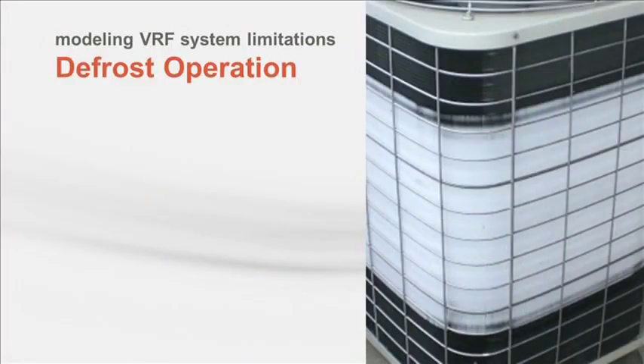Defrost operation allows the outdoor unit to remove any frost and ice buildup on the outdoor coil when operating in the heating mode. Remember that the heat exchanger in the outdoor unit serves as an evaporator when the system is predominantly heating, and this usually occurs when it's cold outside. If a single outdoor unit is used, the system will operate in cooling mode for several minutes, so hot refrigerant is routed to the outdoor unit to melt any built-up ice or frost. Of course, when this occurs, the indoor unit discharges cool air into the space regardless of demand. If multiple outdoor units are used, they may be piped together, and the defrost operation may be different with the additional outdoor unit.